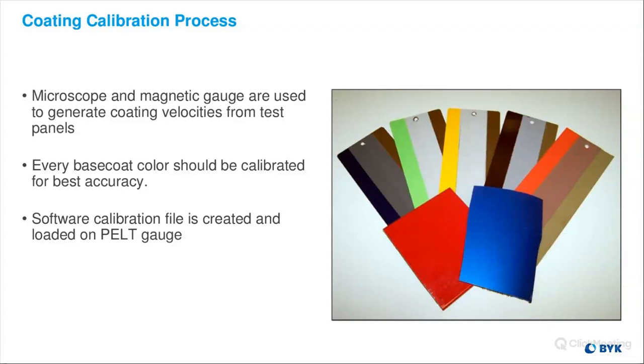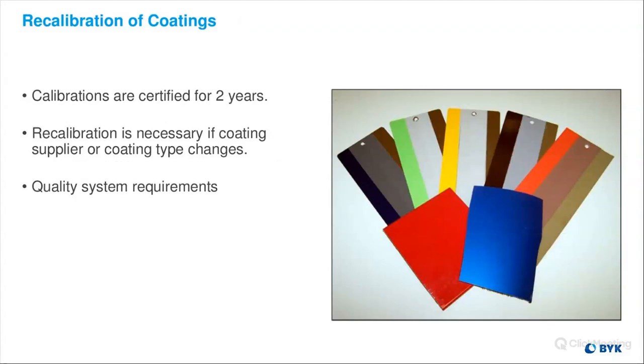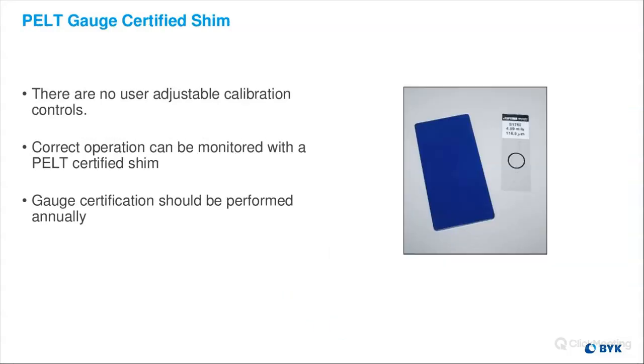You would absolutely want to recalibrate if something changes, such as a supplier or a material. You would definitely want to send a new panel in and have that recalibrated. I got a little bit ahead of myself here on my slide. So again, calibrations are certified, recommended every 2 years. Recalibration is necessary if a supplier or coating type changes, or perhaps it's part of your quality system requirements. You may have it in your quality system that you are to recalibrate your colors every 2 years, or in whatever time frame you specify.